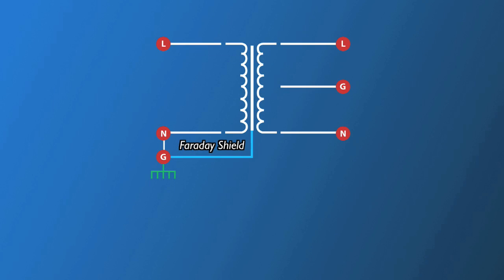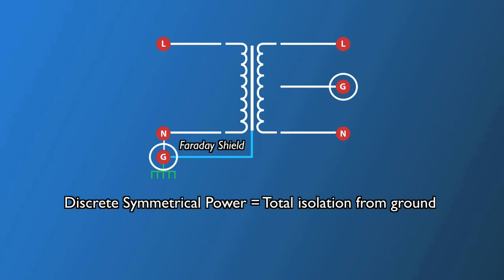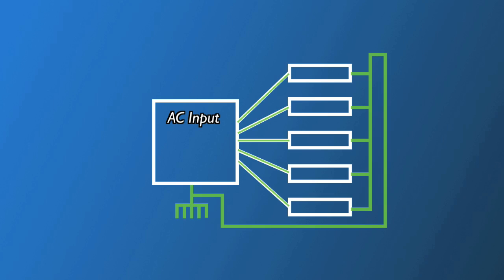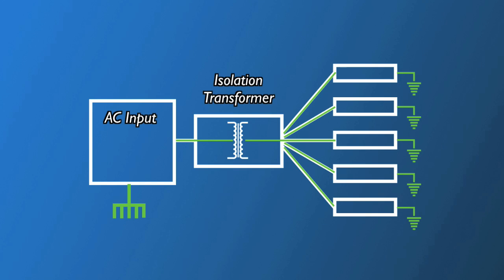Another important attribute with true symmetrical power is total isolation from ground. This has the advantage of breaking the noise that is present on the AC mains, but the greatest advantage is breaking ground loops. Even in a situation where the location is star grounded, one or more remote components can create a ground loop. With an isolation transformer that has an isolated, or floating, output, we may effectively isolate one or more offending components, thus breaking the noise loop.